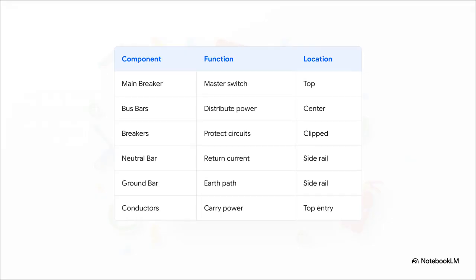And this brilliantly illustrates the exact anatomy of how all those components fit together in one space. You've got the main breaker at the top, setting the total ampacity limit. The busbars run down the center, and those individual circuit breakers clip right onto them. You'll also notice the neutral bar and ground bar on the side rails. Those basically complete the system by returning current to the utility and providing a safe path straight to the earth if there's ever a fault.